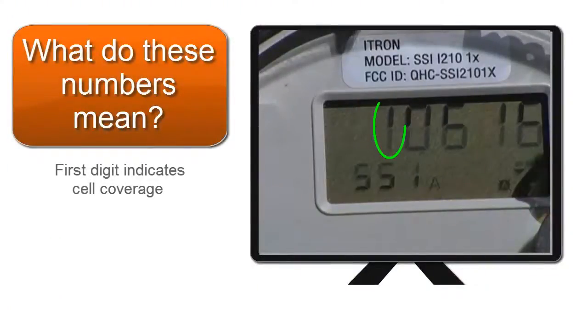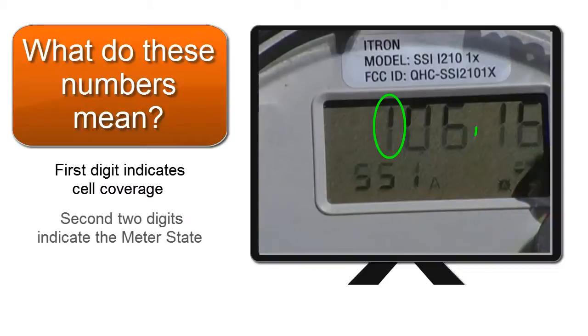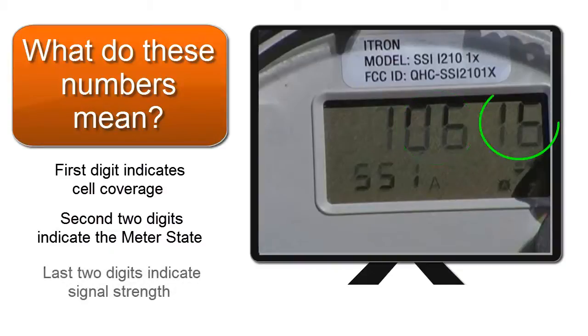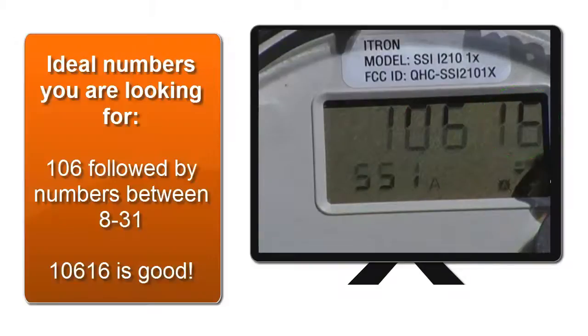So what do these numbers mean? The first digit indicates cell coverage. One is your golden number. The second digit indicates the meter state. 06 is your magic number here. The last two digits indicate signal strength. Numbers 8 through 31 are adequate to connect to the network.